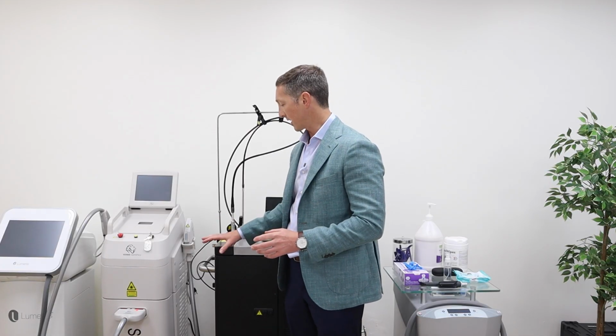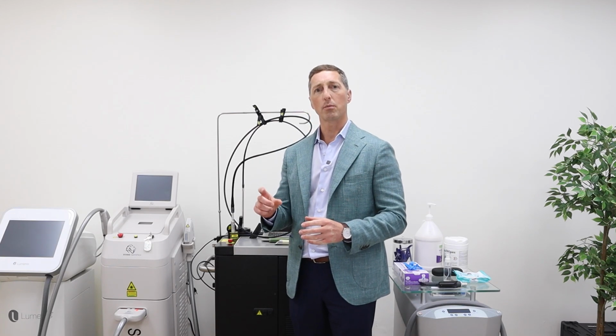So that's why it's so important to really ensure that every single system across all your locations and of course within your same location is verified externally, because otherwise you can imagine it leads to some really poor outcomes for your clinicians and of course clients, right? Your clinicians are going to feel as if one laser system's hot and the other system might be cold or weak. And then of course clients, if treated on the hot system, might incidentally get a hot type of complication, otherwise known as a burn, right? So it's really important for safety and efficacy considerations to make sure that these things are all uniform.